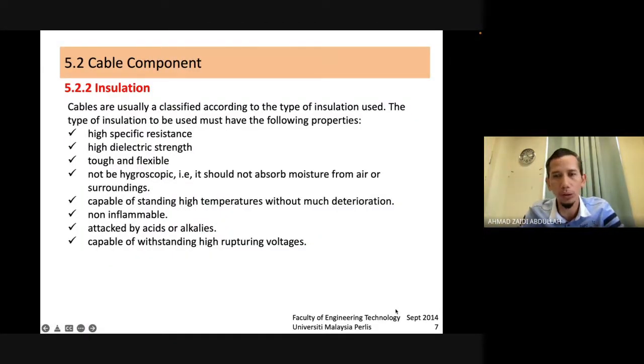Insulation lah, we continue for the insulation. So cables are usually classified according to the type of insulation used. The type of insulation to be used must have the following properties. So make sure in the selection of the cable insulation, we must check at least the high specific resistance, high dielectric strength, tough and flexible, and not be hygroscopic.